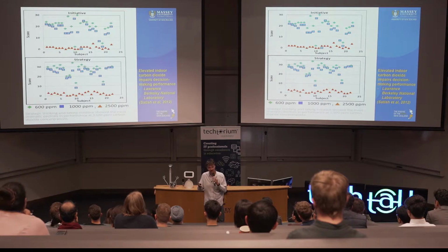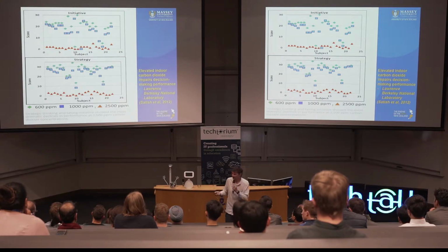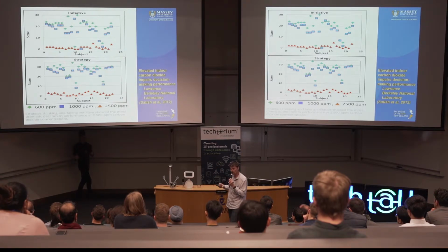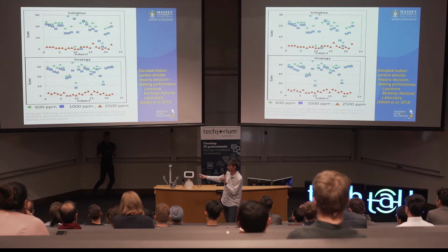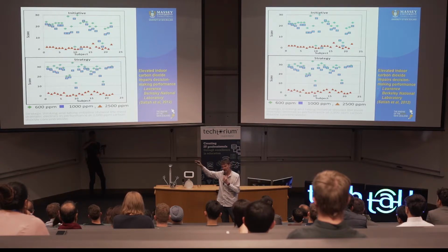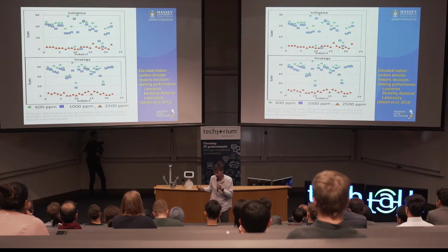And what they did, they asked these 22 students to do some tests, online tests on computers, and this test, they were targeting initiative and strategy. So how much can you do when you are exposed to different level of carbon dioxide? So 600 ppm is exactly what we've got at the moment in this room. We've got some mechanical ventilation, and on the return air going to the end, to the plant room, we've got a CO2 sensor, which is set about 700 ppm, so it's what we've got here. So we are okay at the moment because we've got mechanical ventilation.